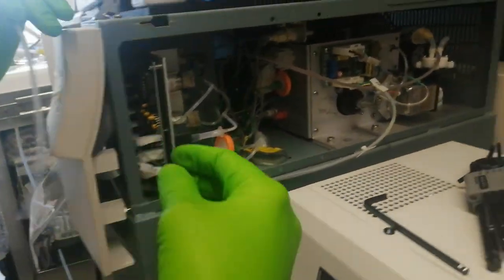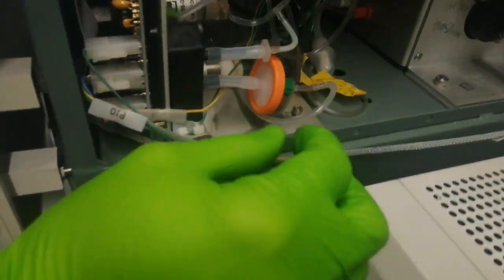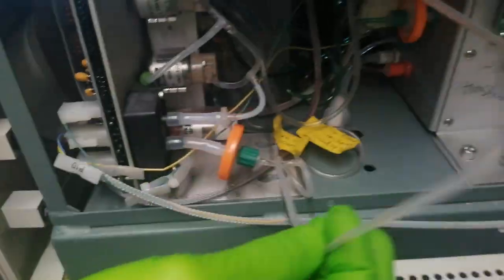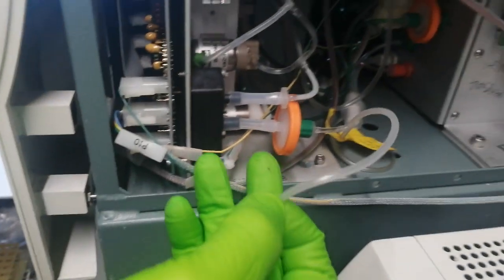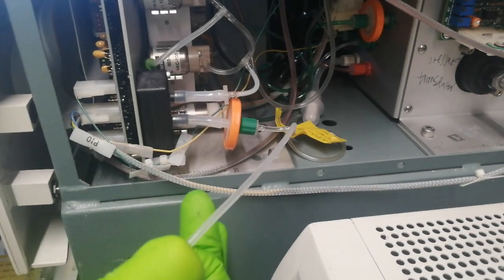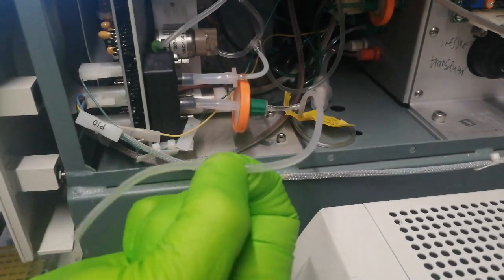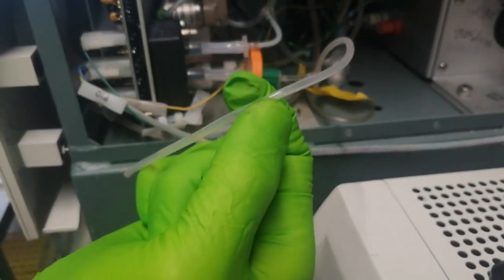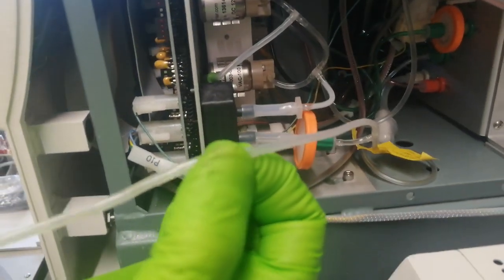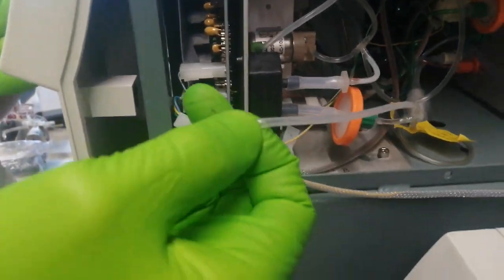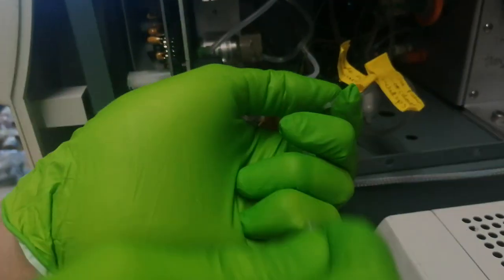So this goes into here, this pinch valve. This is the vent for the sample pressure. When you put the tube on standby, this valve opens. When you're on run, it pinches it closed, and when you put it on standby, it opens. So if you find that you put the tube on standby and the liquid still continues to run, it may be that this thing is staying stuck. That could be because this valve has failed, but more likely it's because the tubing is just fatigued. And that can become a problem. It's more likely to become a problem if you don't use it for a while.